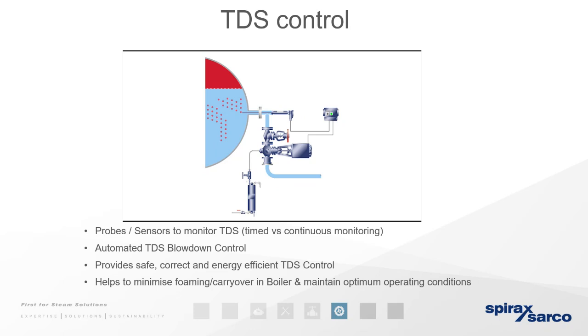Generally, with the boiler OEMs in South Africa, the boiler OEM would be able to tell you, generally speaking, on a packaged boiler, 3,000, 3,500. If it goes more than that, then you do start risking scaling. If you go below that, you do risk blowing down too much, and that becomes inefficient and costly. Yeah, so thanks, Cornelius. Like I said, it will be on the plates for your boilers. As Cornelius said, we use as a standard figure 3,500, but that can differ.